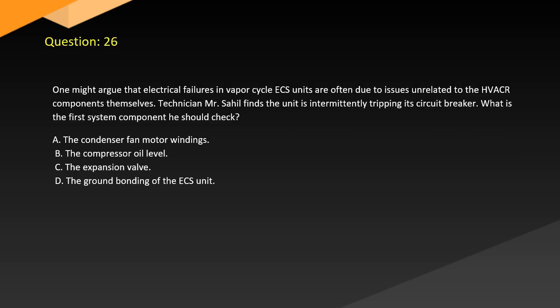Question 26. One might argue that electrical failures in vapor cycle ECS units are often due to issues unrelated to the HVACR components themselves. Technician Sal finds the unit is intermittently tripping its circuit breaker. What is the first system component he should check? A. The condenser fan motor windings. B. The compressor oil level. C. The expansion valve. D. The ground bonding of the ECS unit.